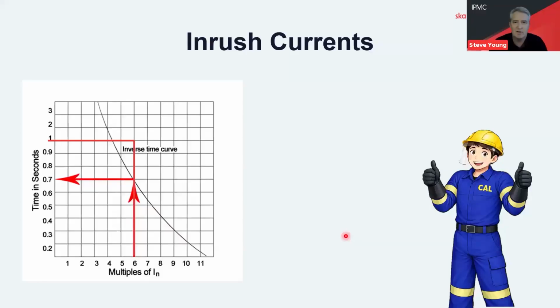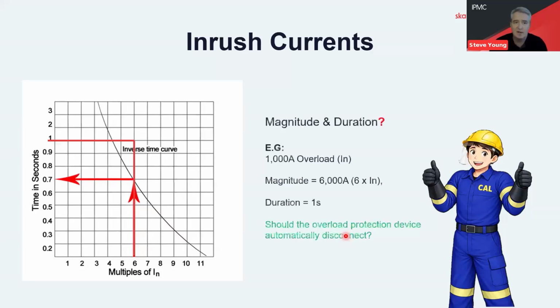Good. So that's correct. For any of you that answered yes, what we're saying is you can see there the extension of the curve has breached that inverse time curve, which means really we expect automatic disconnection of the overload protection.